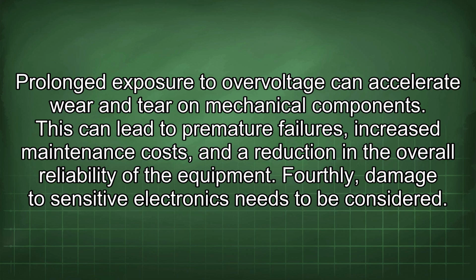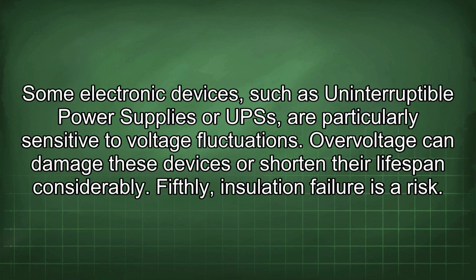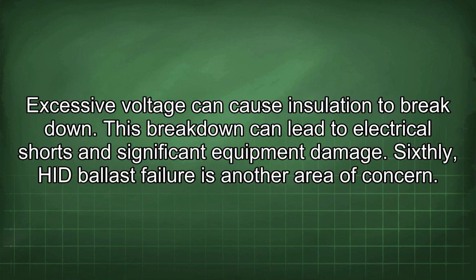Fourthly, damaged sensitive electronics needs to be considered. Some electronic devices, such as uninterruptible power supplies or UPS, are particularly sensitive to voltage fluctuations. Overvoltage can damage these devices or shorten their lifespan considerably. Fifthly, insulation failure is a risk. Excessive voltage can cause insulation to break down. This breakdown can lead to electrical shorts and significant equipment damage.